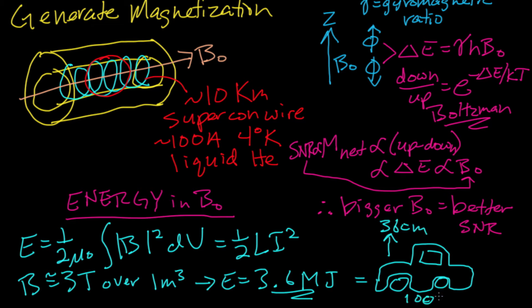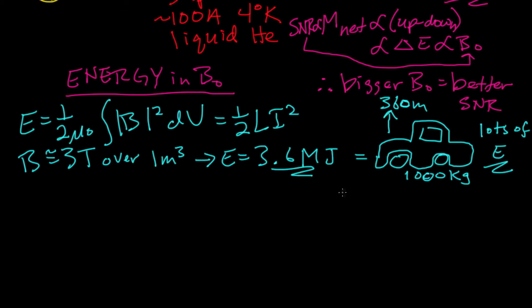If you have a three Tesla scanner, and you're asking the scanner to produce three Tesla over about one cubic meter, the energy that's sitting in that field is about 3.6 megajoules, which is the amount of energy it takes to lift a 1,000 kilogram car 360 meters up in the air. That's a lot of energy. What the system engineer has to do is to figure out what to do with all that energy in the event of a quench.